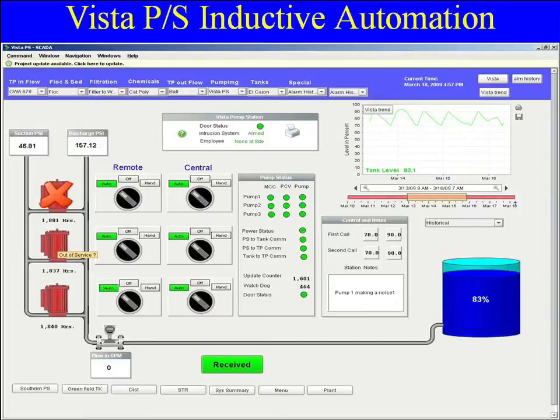I've been able to add out-of-service bits, which are the red X marks. When a pump goes out of service, the operator can highlight it on SCADA. The software has a mouse-over — when the mouse goes over, you can see it asks if you want to mark this pump out of service. And when a change is made, at the top of the screen you get a nice yellow banner that says there's a new project available — click here and it will download the new screens.